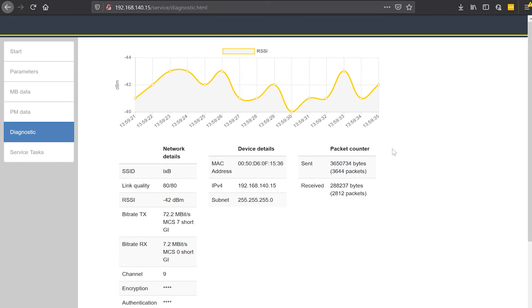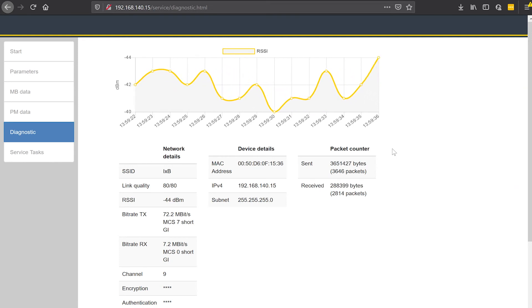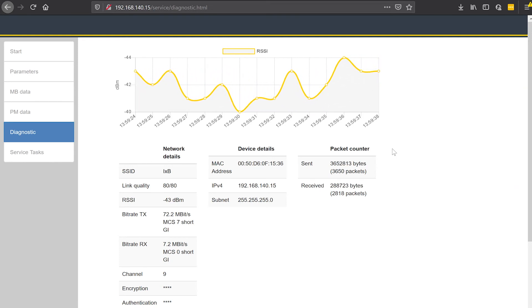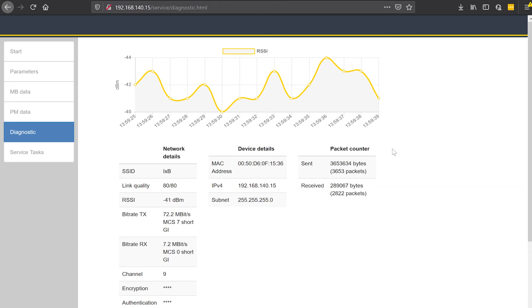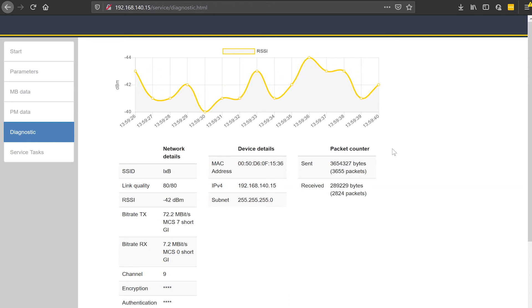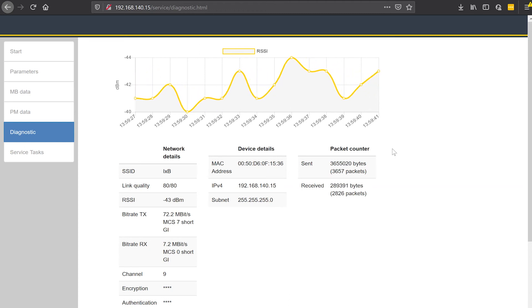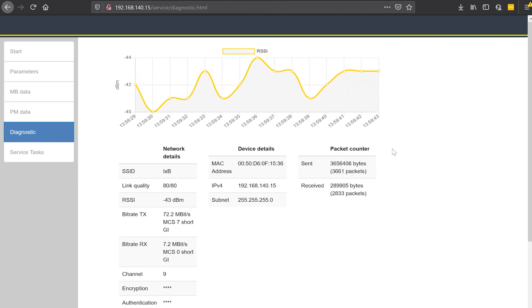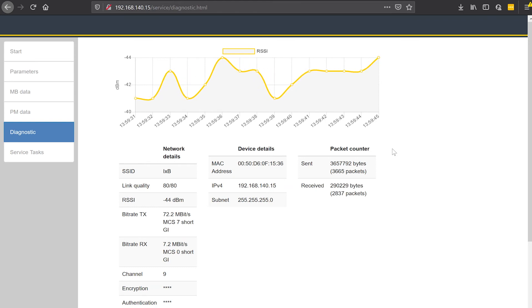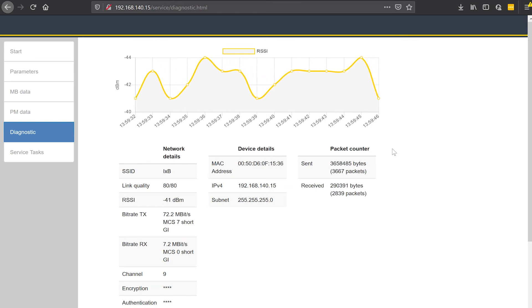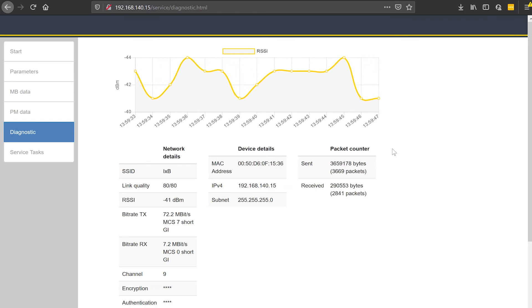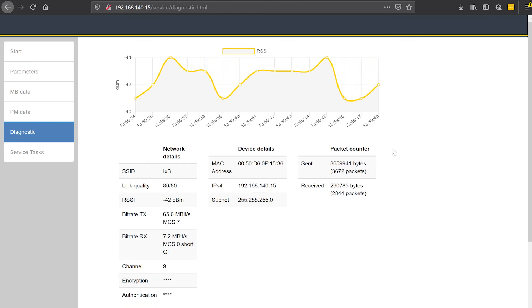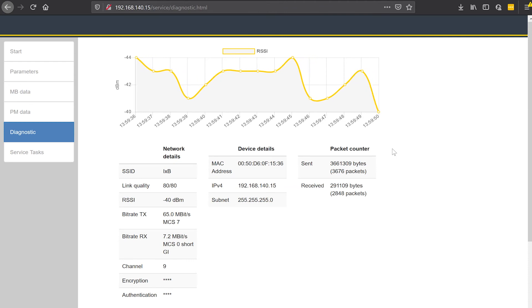That's generally a very good signal. If you have a signal in the negative 40 range, that's great. If you have a signal that gets higher than negative 60, or even worse, higher than negative 70, it becomes more difficult and the tool has to try to retransmit packets more often. That can affect the operation if it gets bad enough.